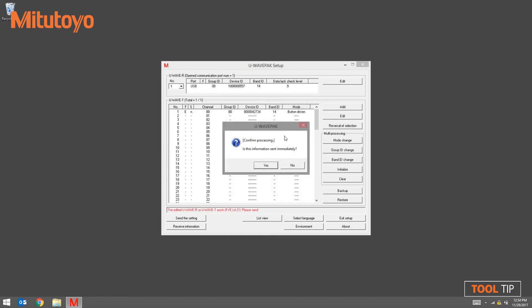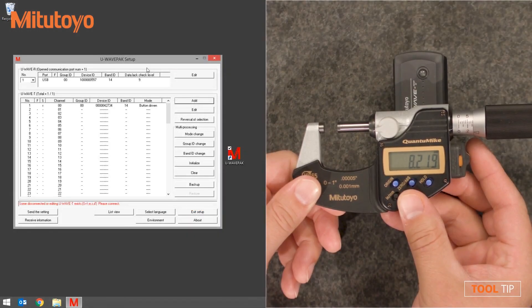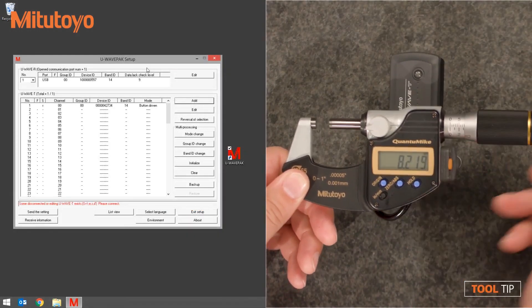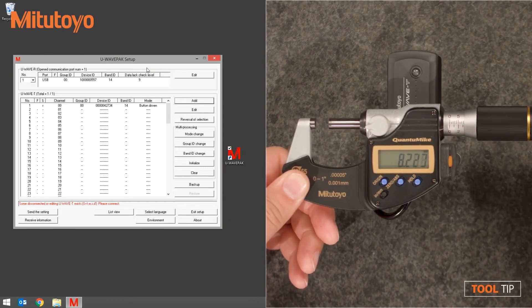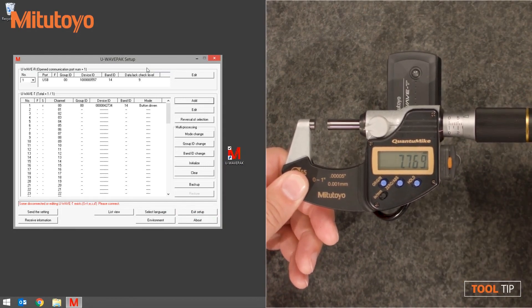The confirmation screen will appear. This means U-WAVEPAK is ready to receive data from the newly added transmitter for the first time. If you're ready to send data from the measuring tool, click Yes. Make sure that your tool is ready to send data and that there's a numeric value on the screen and that it is not in preset mode.